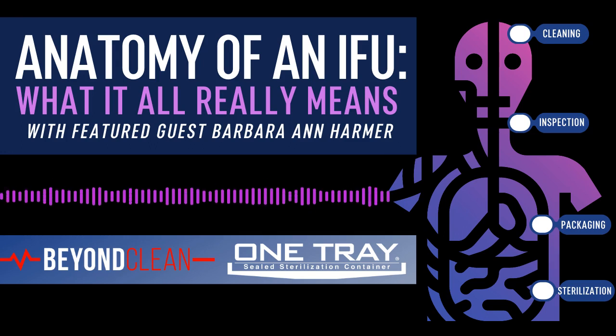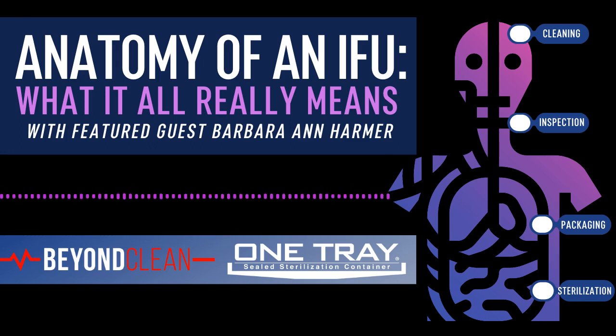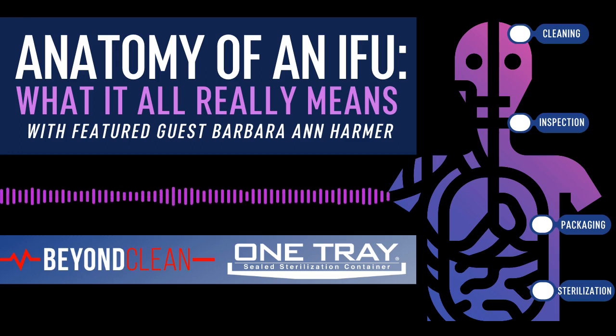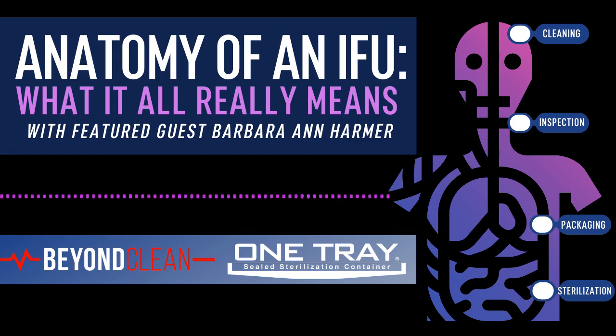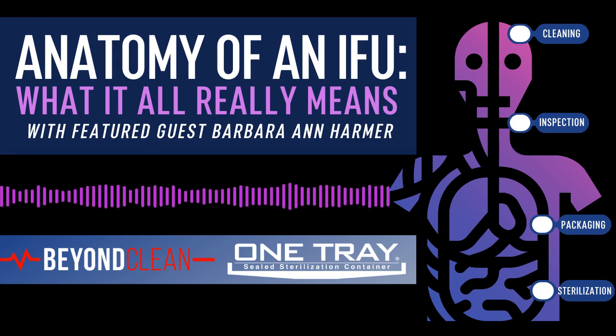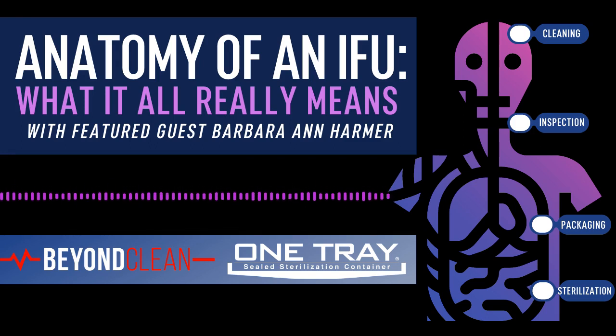It will go on, though, this IFU of the sterilizer, to tell you how the packaging systems should be placed in the sterilizer, the available cycles that could be run, the presets, and custom settings, etc. Now, switching to the second leg of the stool would be the medical device. One would look to this IFU to give you the information on the type of cycles, the exposure time and exposure temperature for each of these cycles. And the third one, which is the jackpot one, especially where ONETRAY is concerned, is the packaging system. And the packaging system, whatever type it is, whether it be wrap, rigid containers, paper, plastic pouches, is where the storage and the dry time comes from.